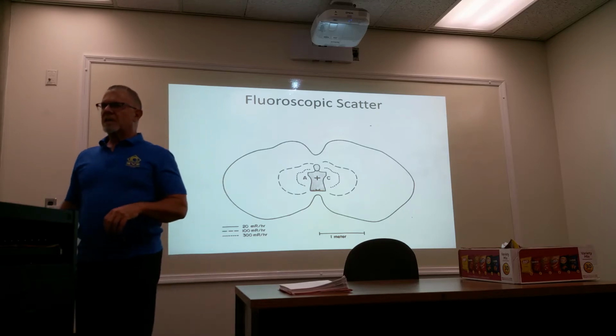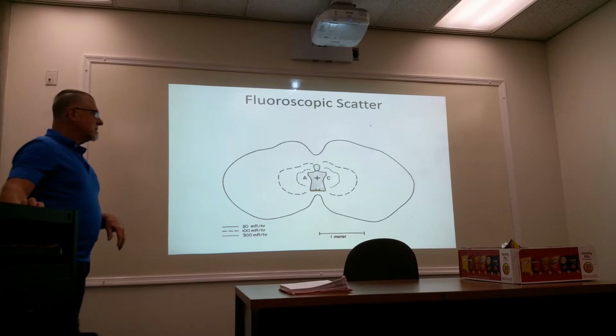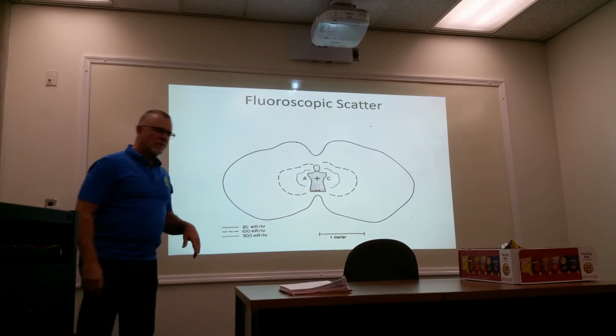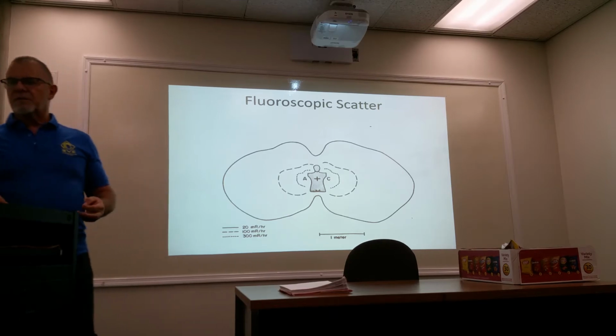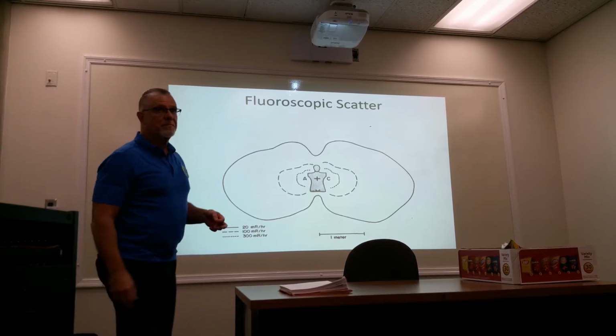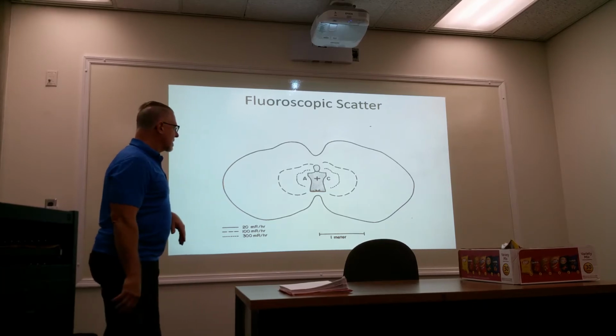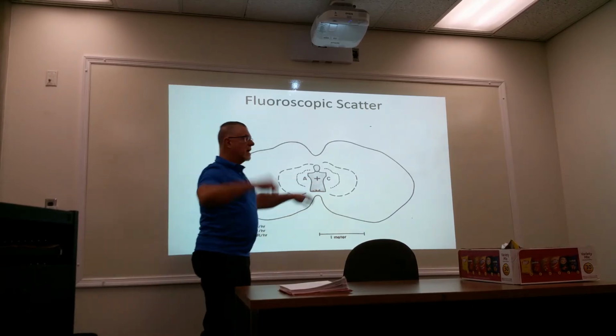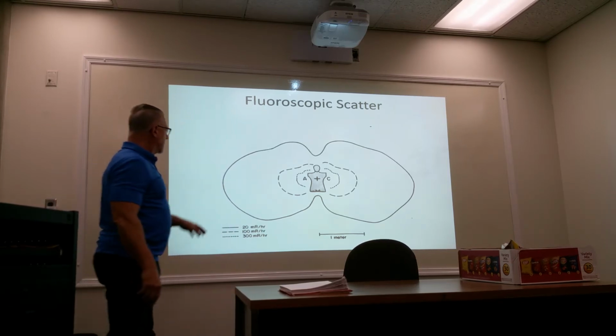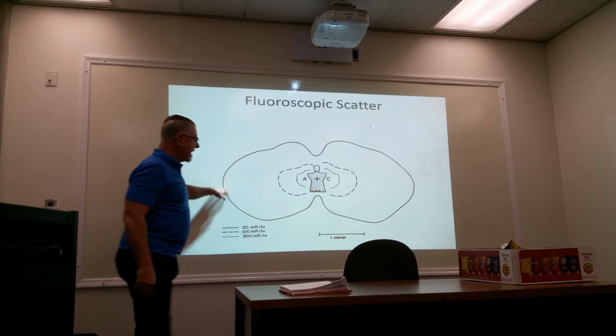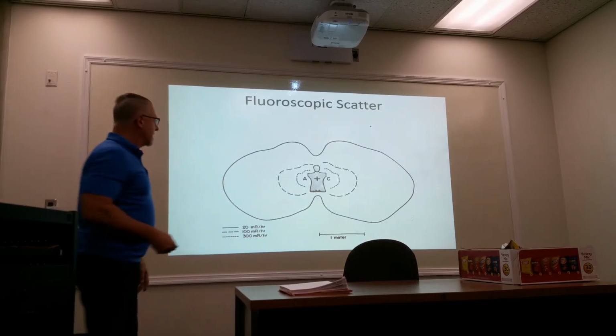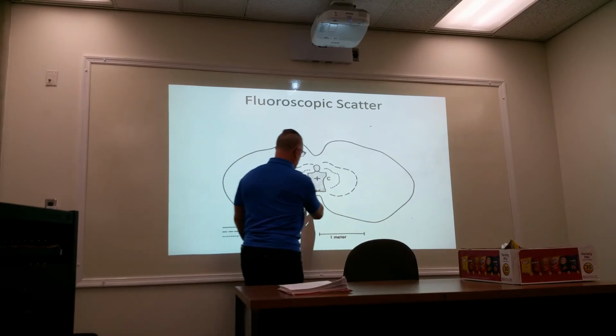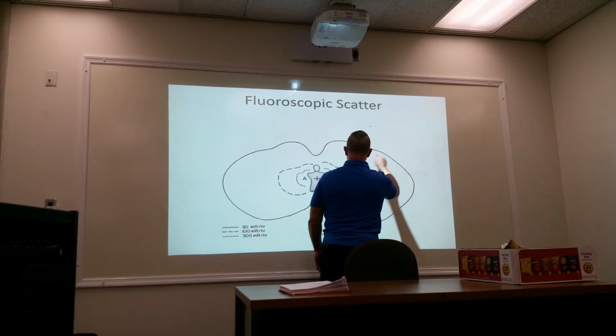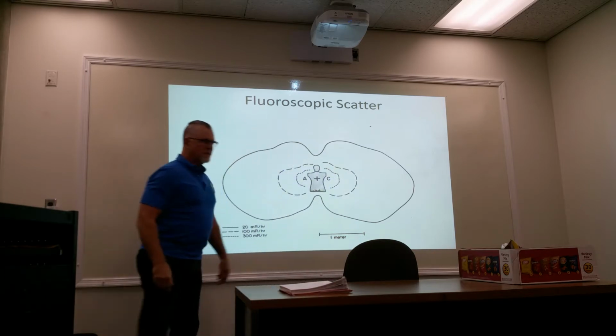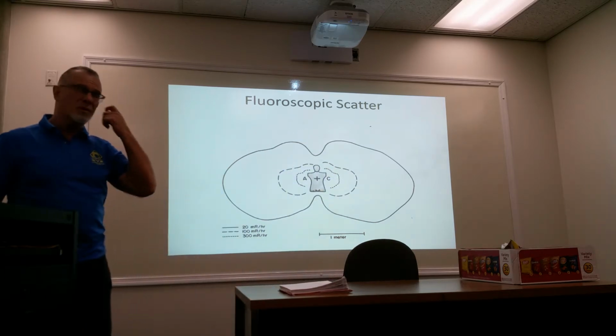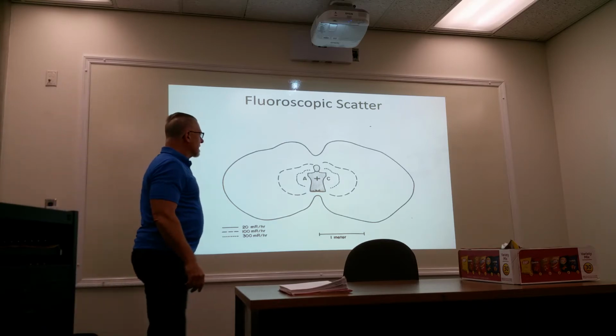Fluoroscopic scatter. This was done with a C-arm. Image intensifier was above. X-ray tube was below. 100 cm SID. Field of view was centered directly over the sternum. So you're basically concerned with mediastinal work. This is a phantom like what you have here. And the poor idiot that did this used a radiation detection device, had the room laid out in a grid, and took individual measurements at certain heights off the floor, at certain distances, and then manually plotted that because there were no computer plots at the time. He would never do it again.